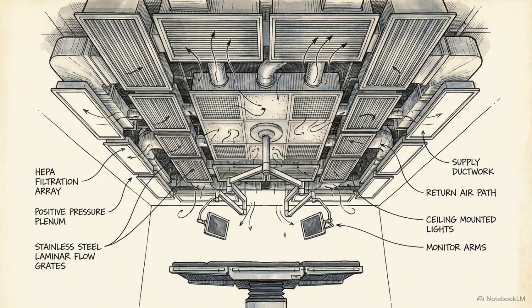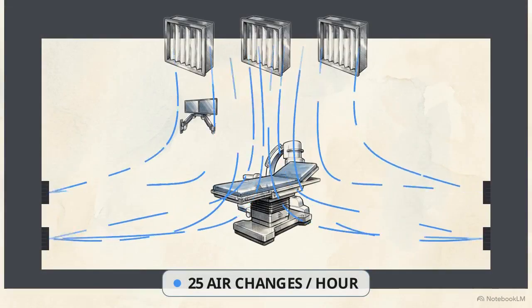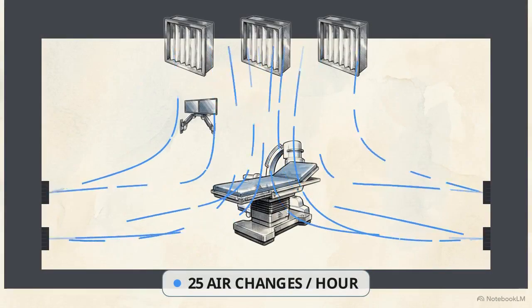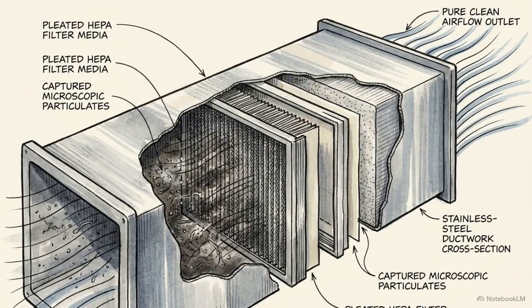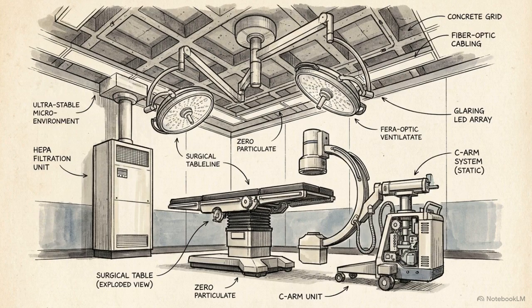Inside the suite, the environmental air quality is aggressively controlled to maintain conditions identical to an open operating room. The HVAC system is specified to perform a minimum of 25 full air changes per hour. It forces this massive volume through high-capacity HEPA filters and seamless stainless steel ductwork to prevent any particulate accumulation. By damping structural resonance and aggressively scrubbing the airflow, engineers create the ultra-stable microenvironment required for complex surgical interventions.